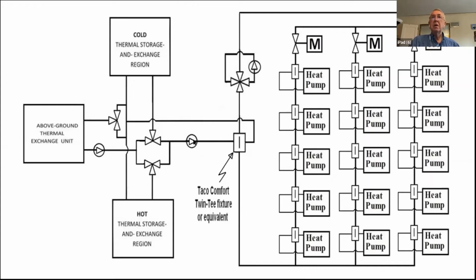So basically, hot water or cold water can come in from the left-hand 3 blocks, and they will condition the water that's in the vertical pipe. And so that vertical pipe can have a large diameter and a large flow rate, and it can flow through this block right here, and it can go either up or down. This four-way valve right here is called a reversing valve. And this water pump is the pump that causes water to flow either up or down in this path.